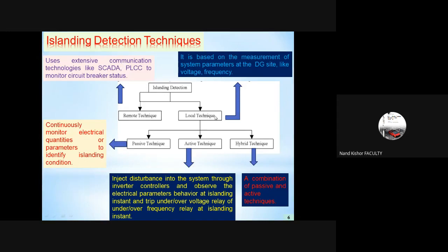Next, in a broad way, is the local technique, using the local signal information. In this case, we have access to the measurement of some signals from the DG location, basically, and it could be signals like voltage or the frequency here. Further, this approach is subcategorized as passive, active, and hybrid techniques. Now, in the case of a passive technique, we continuously monitor these electrical signals to identify the islanding occurrence. That means we monitor the signals continuously at a sample rate, and that gives us the decision whether the islanding event has taken place or not. That is one way. In the second approach, we have the active technique.